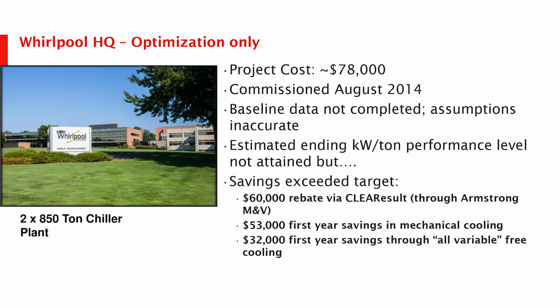When they switched to free cooling, all fans and all pumps ran at 100% speed. It wasn't connected to the BAS. It just went on, so it didn't matter if they needed 50 tons or 200 tons, everything went to full speed. So we introduced the same kind of modular concept for that, and they got a bonus $32,000 just through thinking a little bit differently.